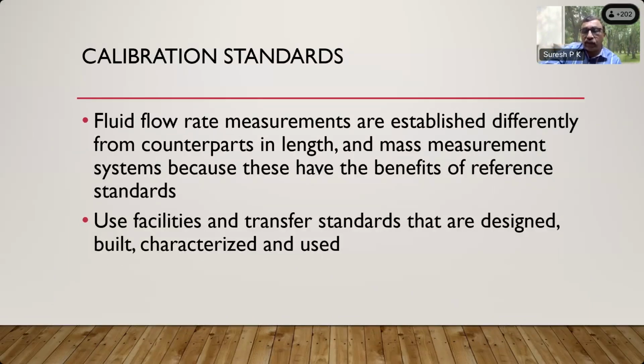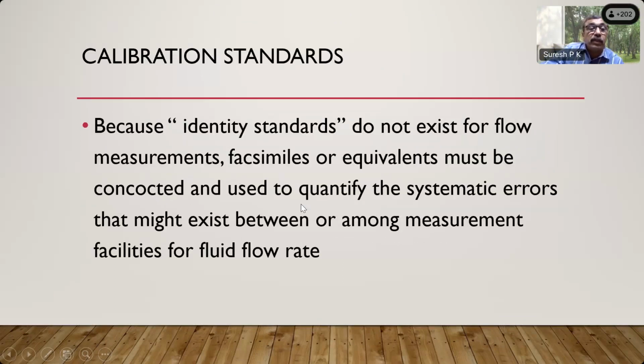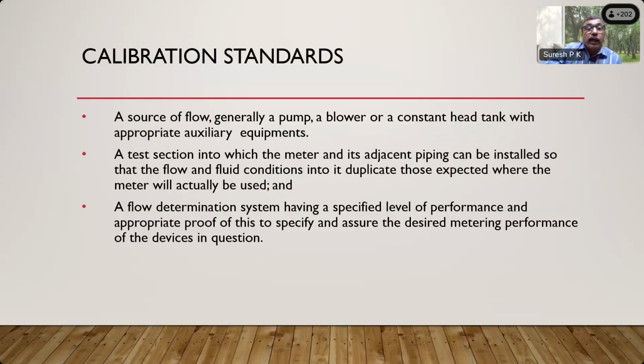Those are some of the flow meters which are generally available in the market. Now, calibration standards, fluid flow, and specific transfer standards. A calibration standard generally needs a source of flow. It's generally a pump. It may be a blower, or maybe a constant head tank with appropriate auxiliary equipment. It needs a test section into which the meter and its adjacent piping can be installed, for providing or duplicating the flow conditions expected in the operating conditions. It also needs a flow determination system having a specified level of performance and appropriate proof to assure that performance.